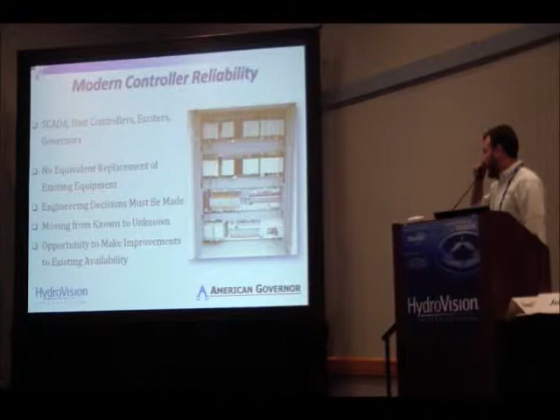Now, why is this relevant now? There is a trend, as most of you know, towards modernizing controllers. This can be SCADA systems, unit controllers, excitation systems, governors. I'll probably reference governors a little more because that's what I'm familiar with, but these principles apply to all types of modernized control. So if you have a relay board, a pilot exciter, and a mechanical governor, and you're replacing it, there is no equivalent replacement to what you have right now.